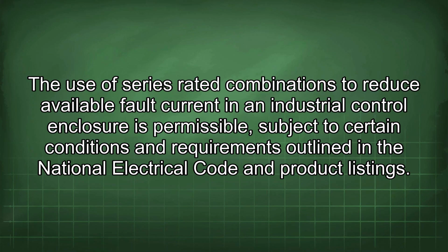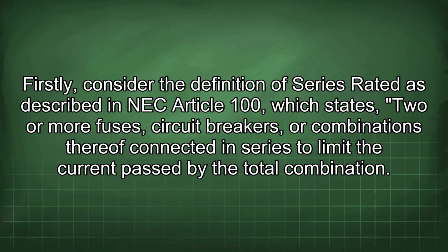The use of series-rated combinations to reduce available fault current in an industrial control enclosure is permissible, subject to certain conditions and requirements outlined in the National Electrical Code and product listings. Firstly, consider the definition of series-rated as described in NEC Article 100, which states 2 or more fuses, circuit breakers, or combinations thereof connected in series to limit the current passed by the total combination.